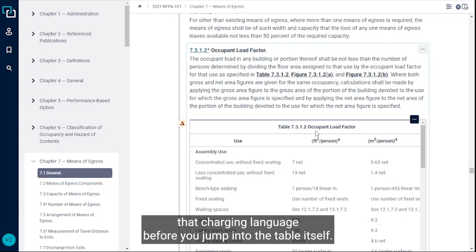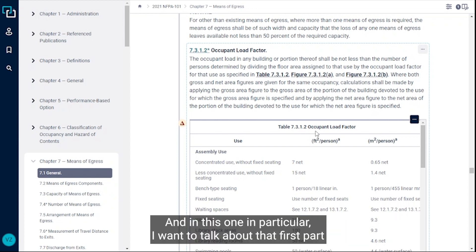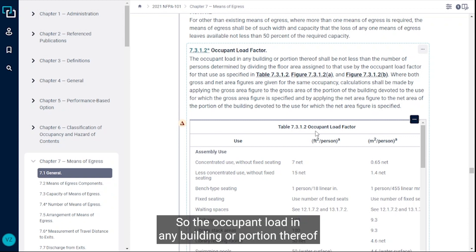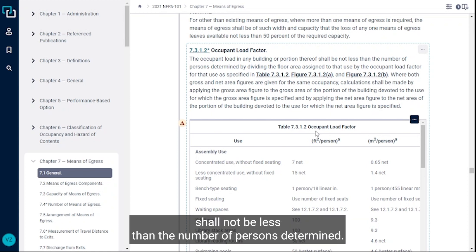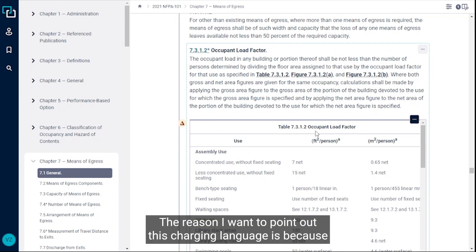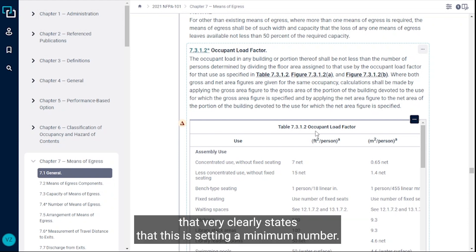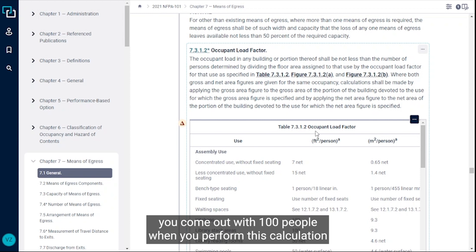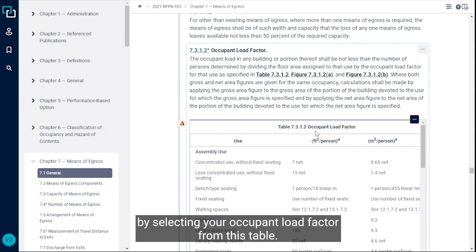In this one in particular, I want to talk about that first part of that first sentence. The occupant load in any building or portion thereof shall not be less than the number of persons determined. The reason I want to point out this charging language is because it very clearly states that this is setting a minimum number. If you do your calculation and let's just say you come out with a hundred people when you perform this calculation by selecting your occupant load factor from this table, but you know that that space is going to have 150 people, you need to use the larger number, which would be 150 people. This is setting a minimum.